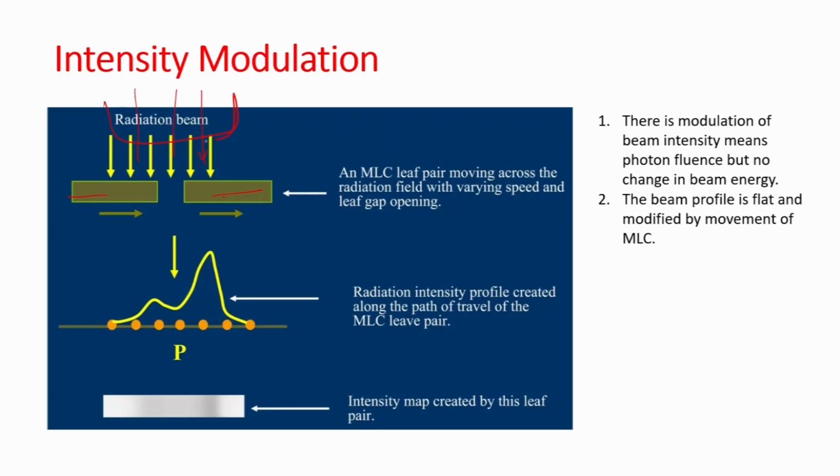Your beam profile is flat. This is your actual beam profile before the MLCs. How does this flat beam profile become like this? This is the modulated beam profile.